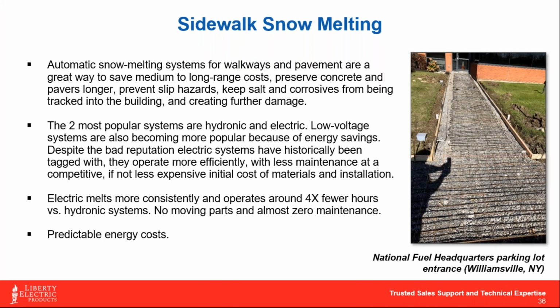what's really neat about this is I think the heat delivery is incredibly consistent versus a hydronic system. When we heat water glycol, we're pushing it out, and where it's hitting, say, the sidewalk at 120 degrees or 140 degrees when it comes out, by the time that glycol's gone through its path or its zone, it's coming back into the boiler at maybe 70 degrees, 80, 70, who knows, 60. Now, it's great for the condensing effect on the boiler itself, and it increases its efficiency greatly.